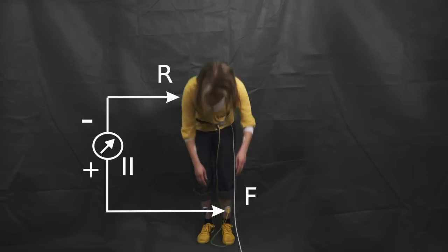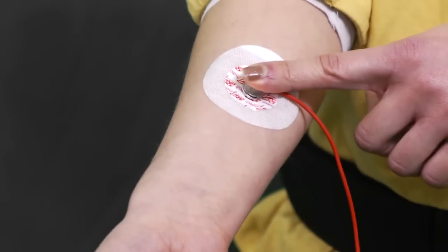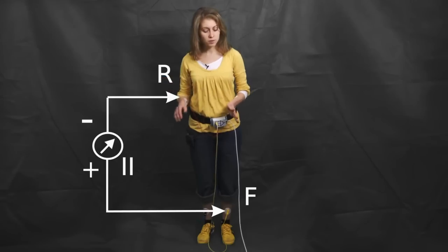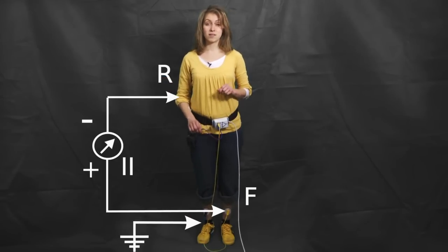For Einthoven II, the negative input — my red cable — is connected to the right arm. And ground, the blue cable, stays connected to the right foot.